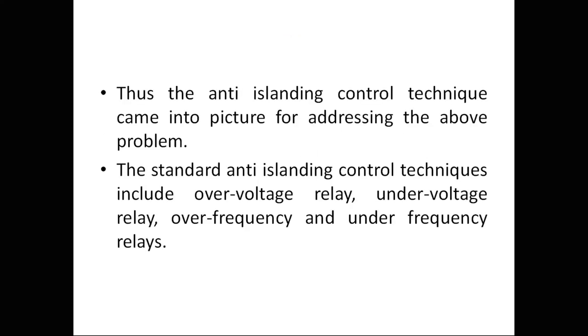To address the islanding problem, anti-islanding control techniques are used. Standard anti-islanding control techniques include over-voltage relay, under-voltage relay, over-frequency relay, and under-frequency relay. These relays are used for anti-islanding protection. These are the main grid issues when connecting distributed generation, especially PV systems, to the electric power grid.